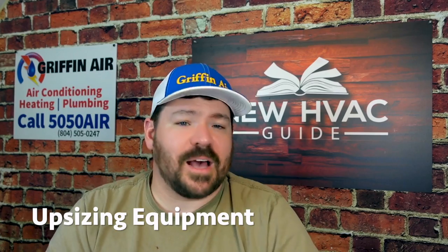Number five: upsizing the equipment just to upsize it. This kind of goes back to the heat load calculation issue. I can tell you in Virginia, where we're located near the water, humidity is a big deal. If you oversize equipment, not only does it short cycle, but it can create mold and mildew problems because of the humidity in the air.